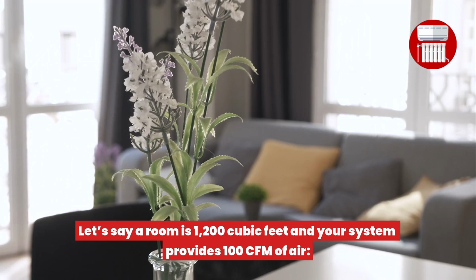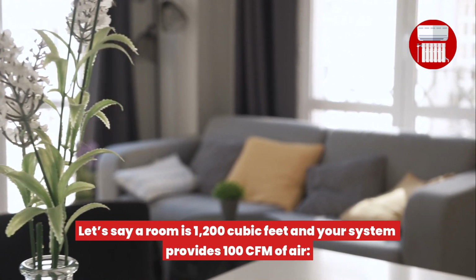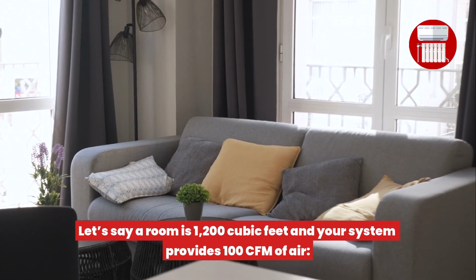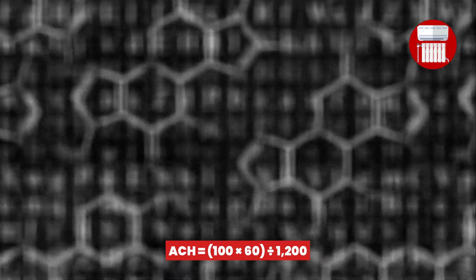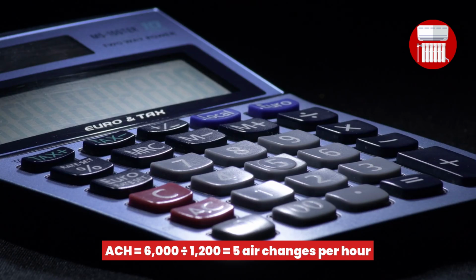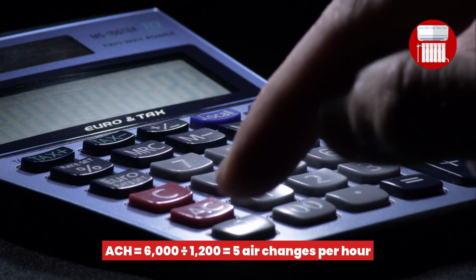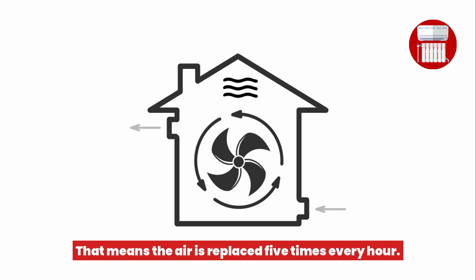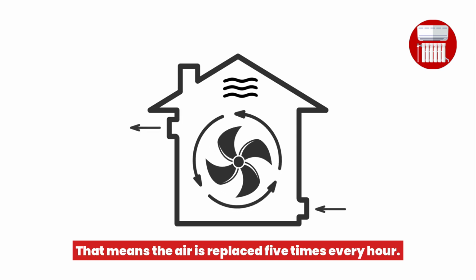Example breakdown. Let's say a room is 1,200 cubic feet and your system provides 100 CFM of air. ACH equals 100 x 60 divided by 1,200. ACH equals 6,000 divided by 1,200, which equals 5 air changes per hour. That means the air is replaced 5 times every hour.